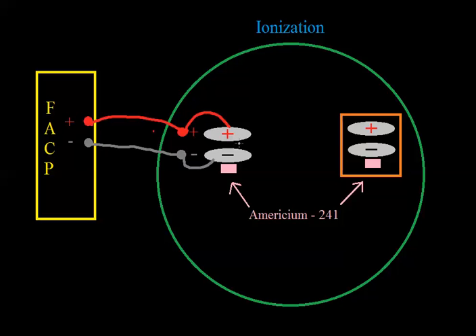The electron, which is a negatively charged element, is attracted to the positive charge. So the electrons, which are now free, are flowing towards the positive plate. Now the oxygen and the nitrogen have a positive charge because they lost that negatively charged electron. So now they are ionized—hence the name ionization—and they are attracted to the negative plate.